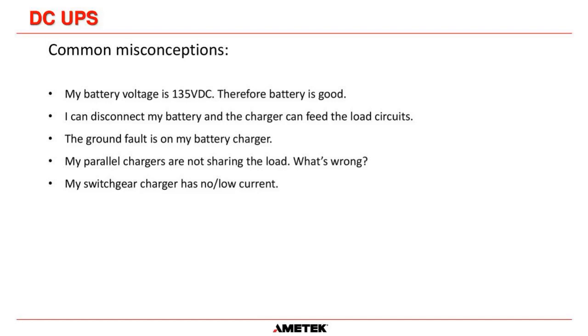So common misconceptions. And the first one is, for a 60 cell system, my battery voltage is 135 volts. Therefore, the battery must be good. Okay, we'll go into that in a minute. The second one is, I can disconnect my battery from the charger and the charger will feed the load circuits without any issues. Then we have the ground faults on chargers, very common misconception there. Oh, parallel, I knew I went into this later. Parallel chargers are not sharing, what's wrong? And then my switchgear charger has no low current. So we'll go over each of these individually.